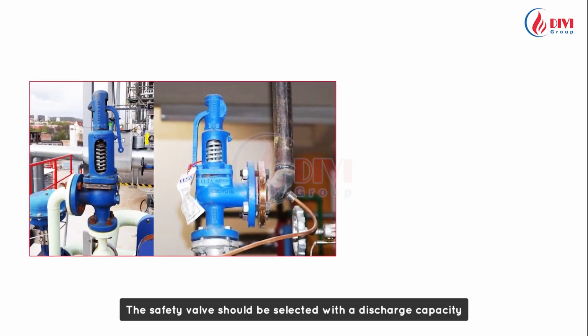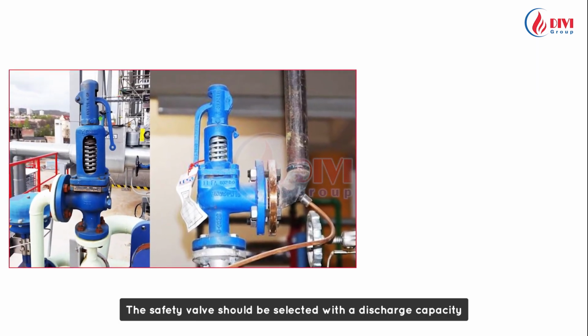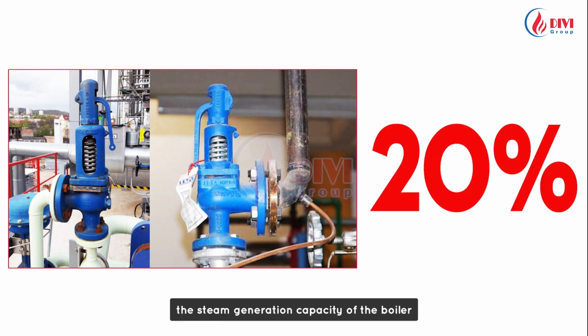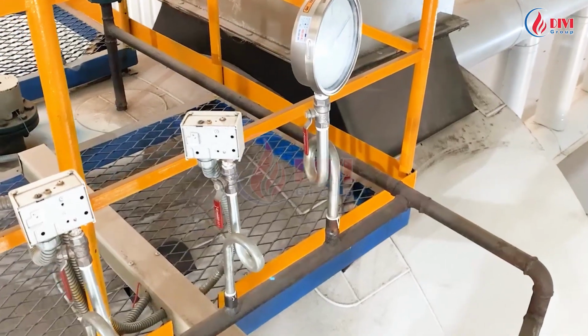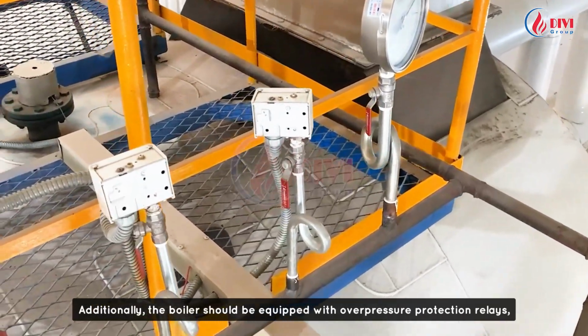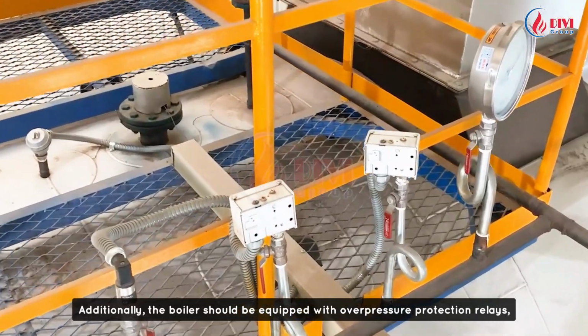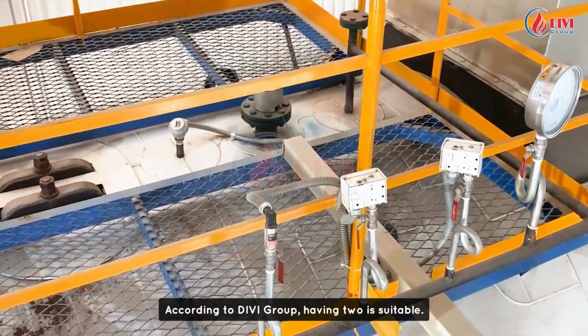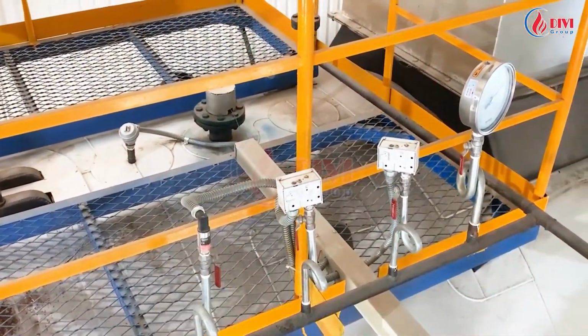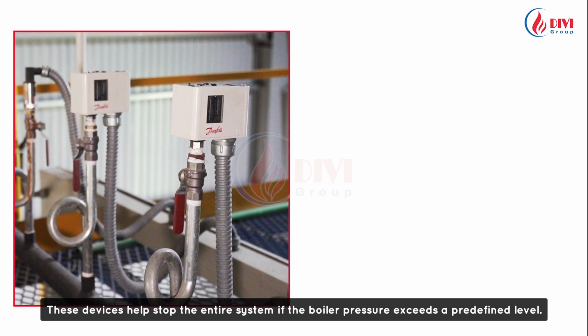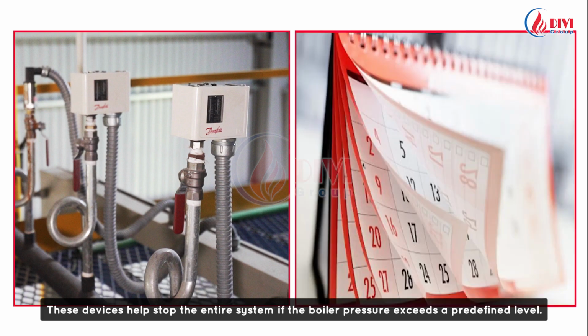The safety valve should be selected with a discharge capacity at least 20% higher than the steam generation capacity of the boiler to ensure complete release in case of overpressure incidents. Additionally, the boiler should be equipped with overpressure protection relays, with at least 1 installed, according to DIVI Group, having 2 is suitable. These devices help stop the entire system if the boiler pressure exceeds a predefined level.